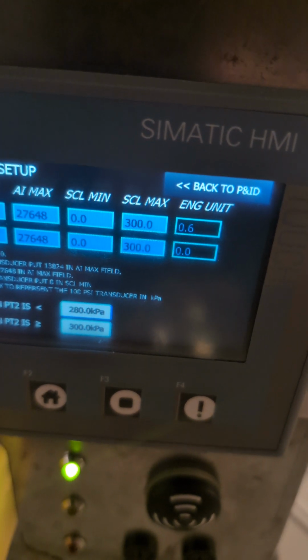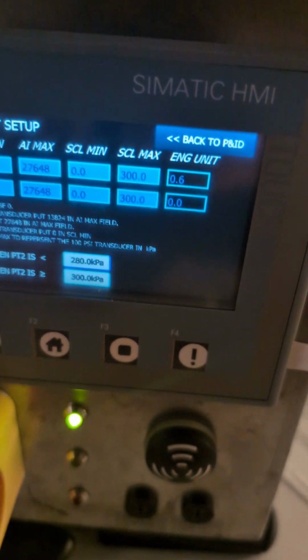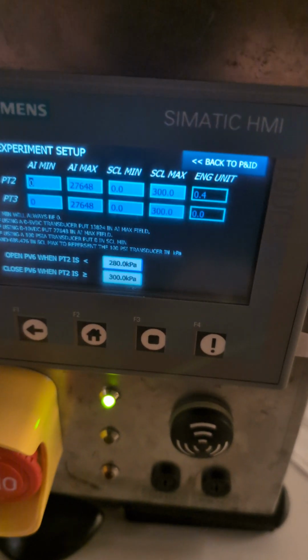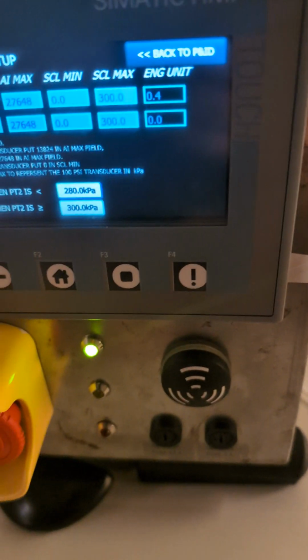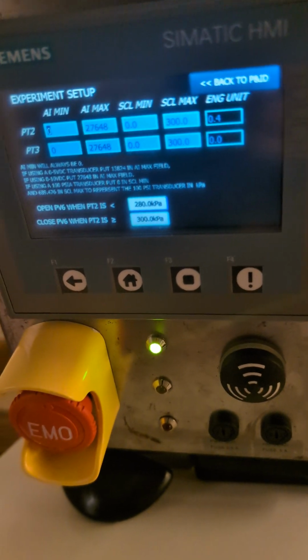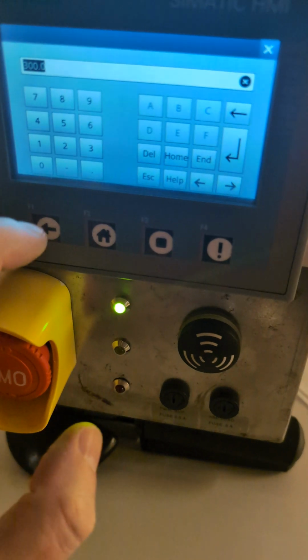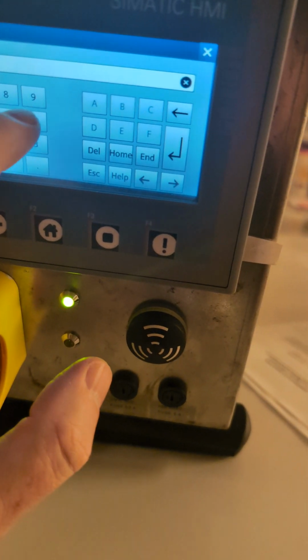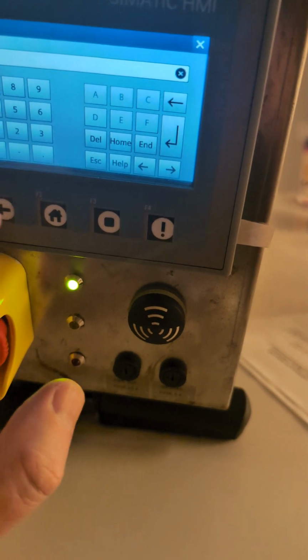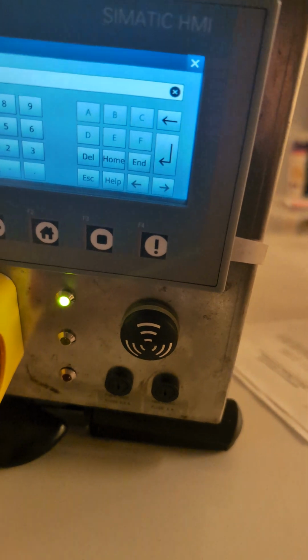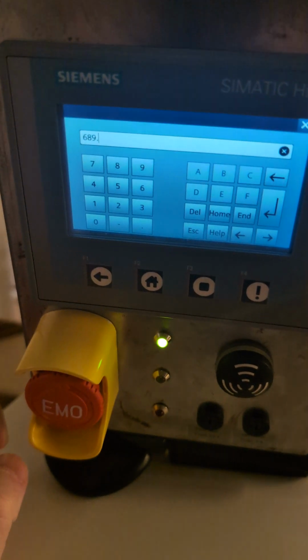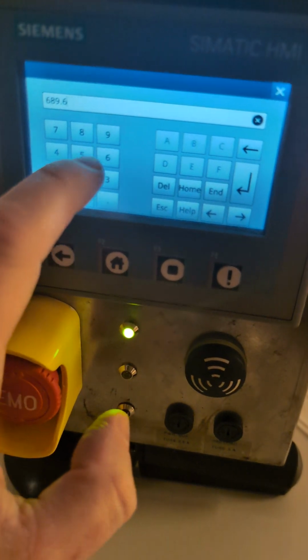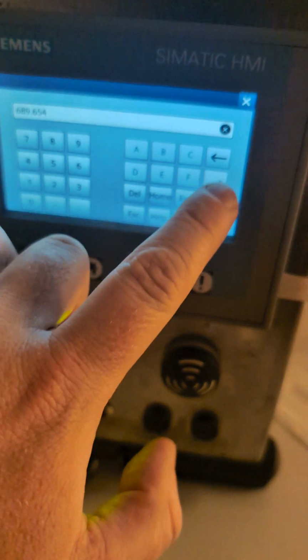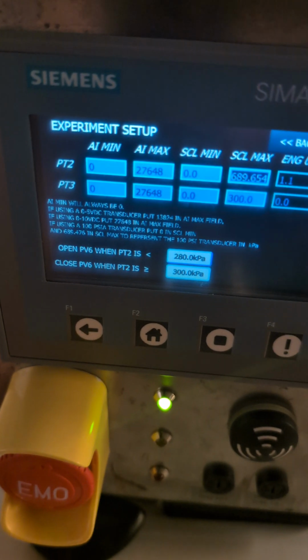Then scale min is going to be 0. Just say you've got a 100 PSI pressure transducer and you want to read it in kPa, you're just going to go here and put in 689 point... I forget what that is, 654, I'll just put that in for now. Press that, and now you've set up your PT2.